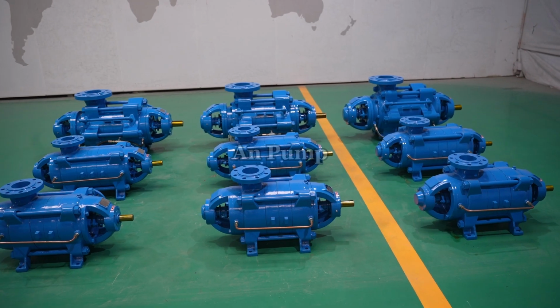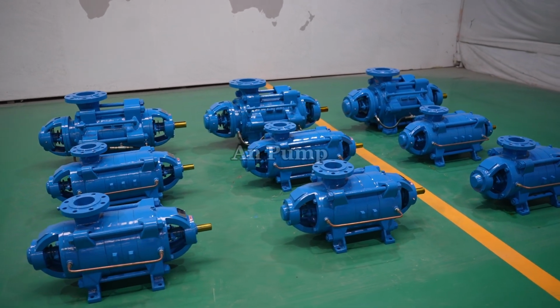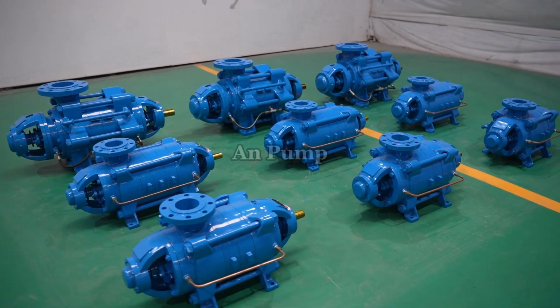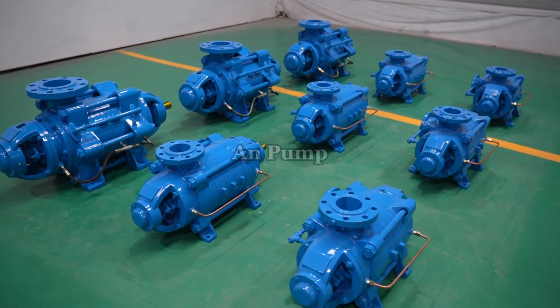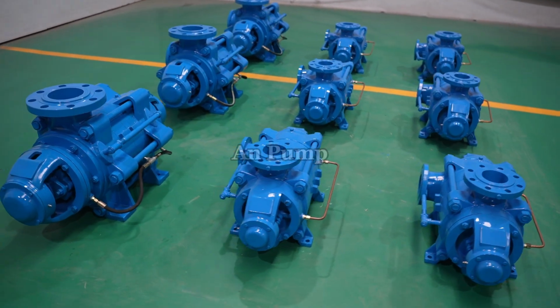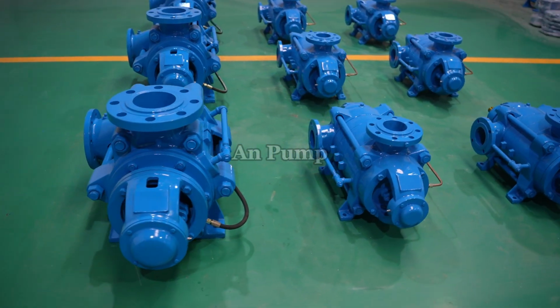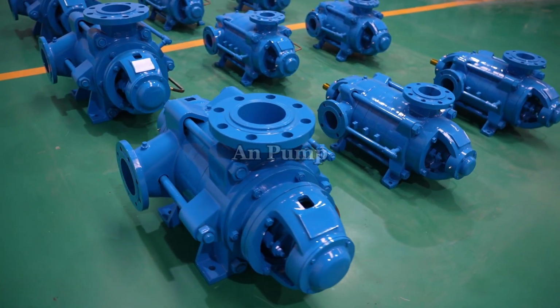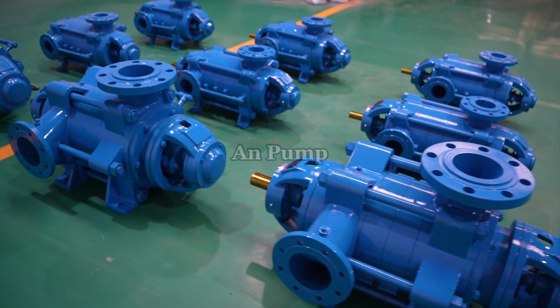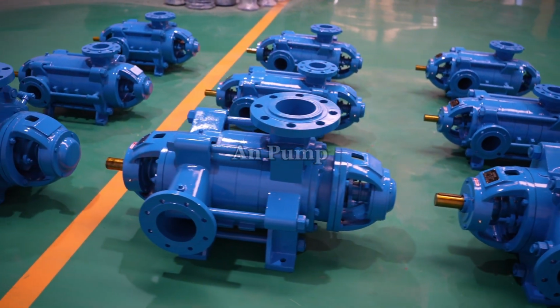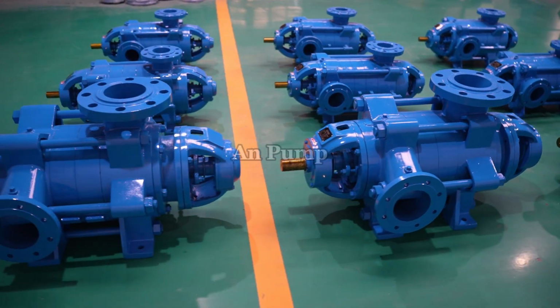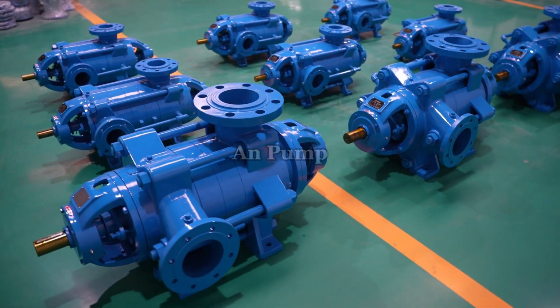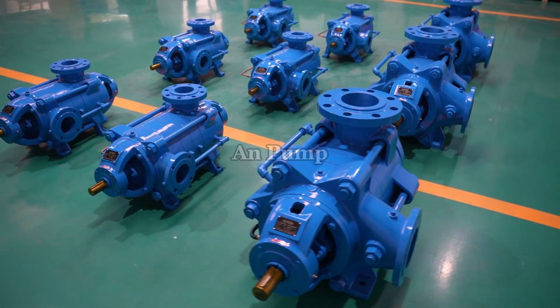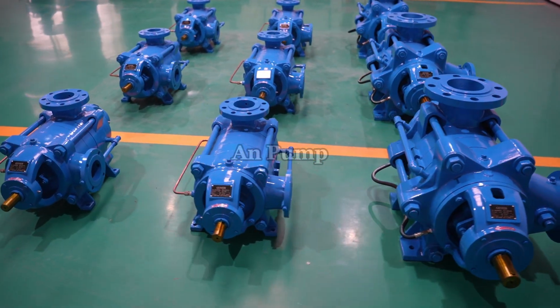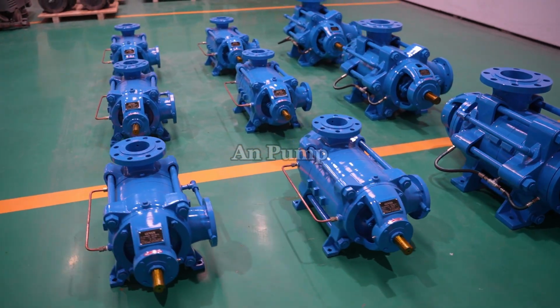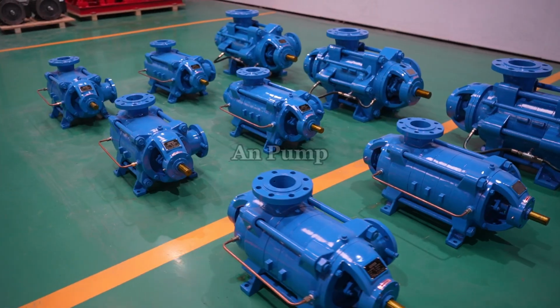Type number 3, the multistage centrifugal pump. When one impeller isn't enough to generate the pressure you need, you go multistage. These pumps have 2 or more impellers arranged in series inside a single casing. Each stage adds more head. A 4-stage pump develops about 4 times the pressure of a single-stage pump with the same impeller size. In a horizontal multistage pump, fluid enters the first impeller, then flows into a diffuser or crossover passage, then enters the second impeller, and so on until it exits at the final discharge. Some designs face all impellers the same direction, while others alternate directions to balance axial thrust.